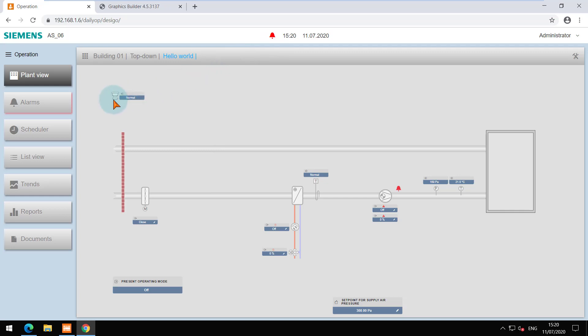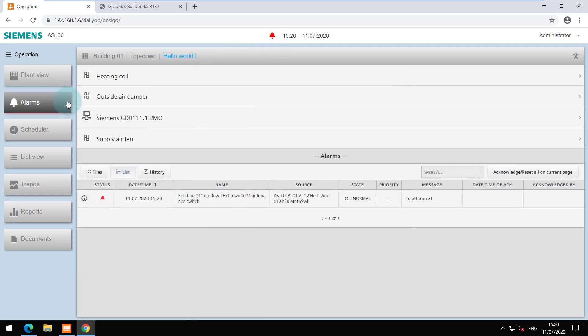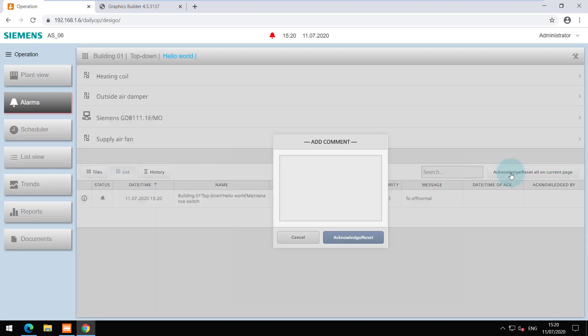Navigate to alarms tab to see the details. The state is currently off normal and when I switch it back it goes to normal. According to the notification class, the alarm needs to be acknowledged and you can do that from here. Enter the comments and the alarm will be acknowledged.